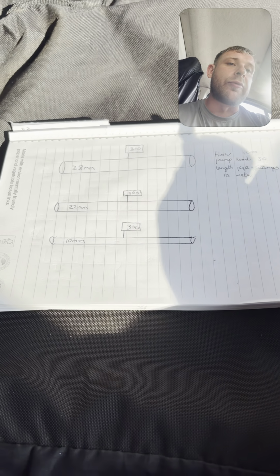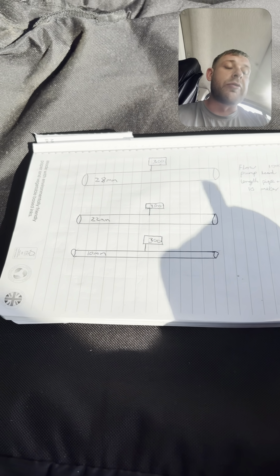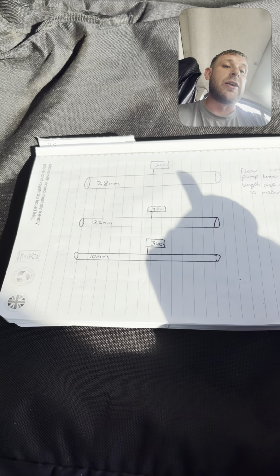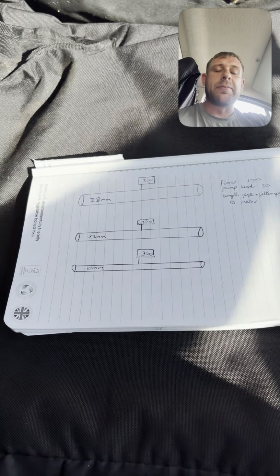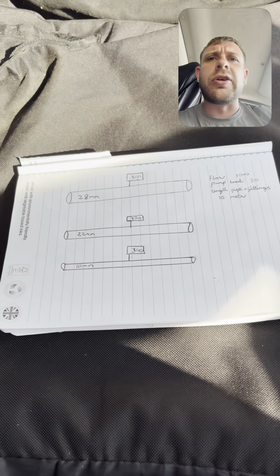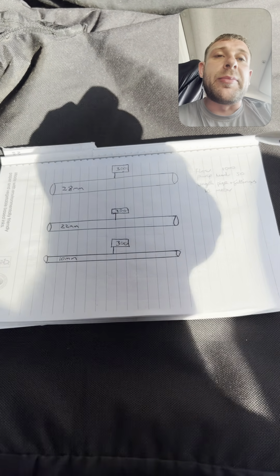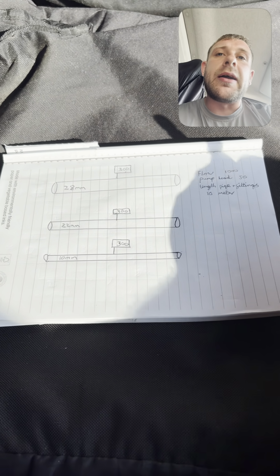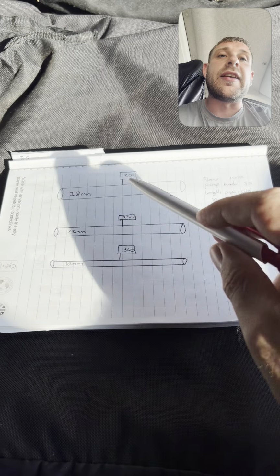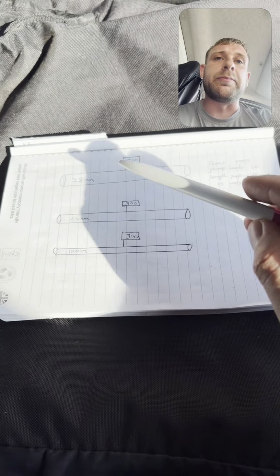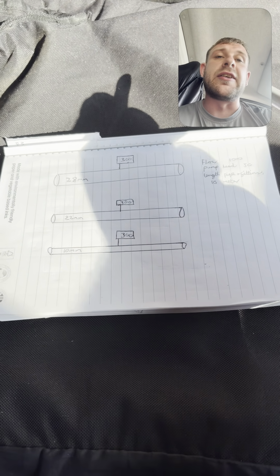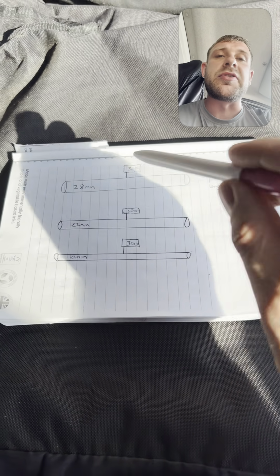We'll run through situations where we may need to upgrade some pipe, or ways around it if the 10mm pipe didn't work. There's a few different variables we look at when we're looking at 10mm pipe. The system's always going to need a specific flow rate, and different radiators are going to need different flow rates depending on the outputs of each room.